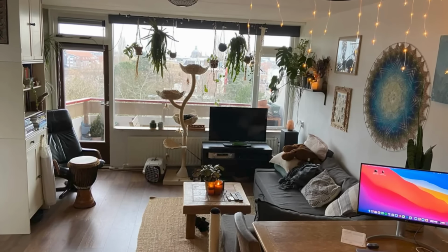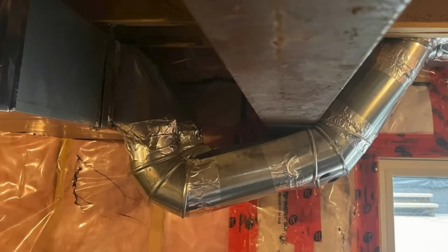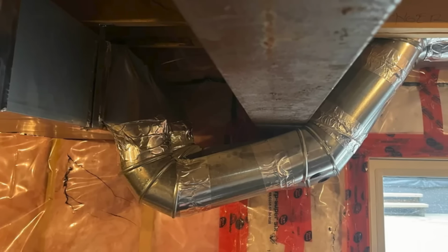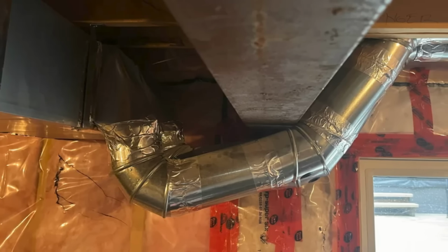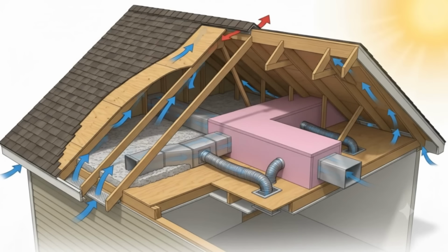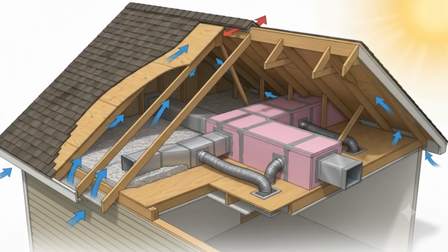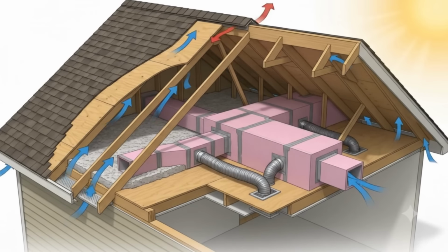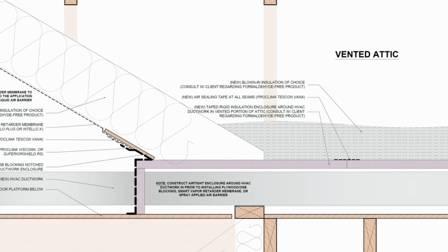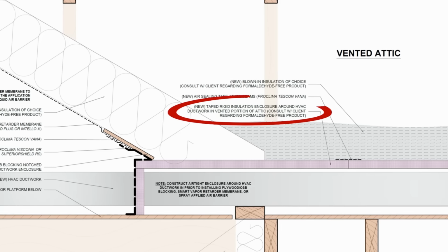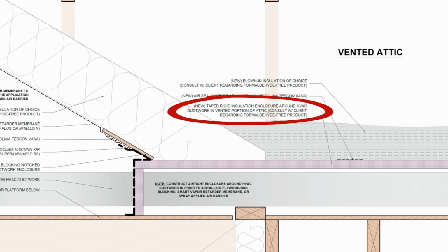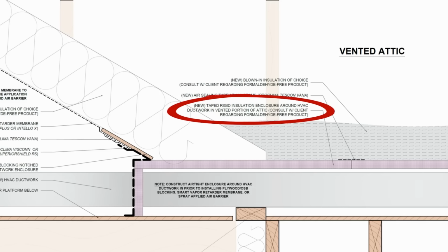Sometimes, because of tight floor plans, vaulted ceilings, or complex retrofits, you simply can't find the space inside the living area for all those bulky ducts. Now, sometimes in very specific building conditions, it's possible to construct an airtight insulated enclosure box around the ductwork and trunk lines using rigid foam insulation so that the ducts are still coupled to the interior space while still allowing you to maintain that vented attic.